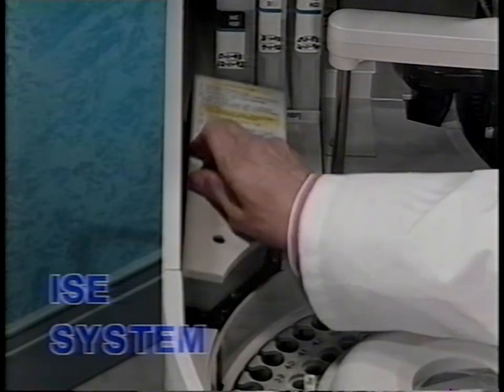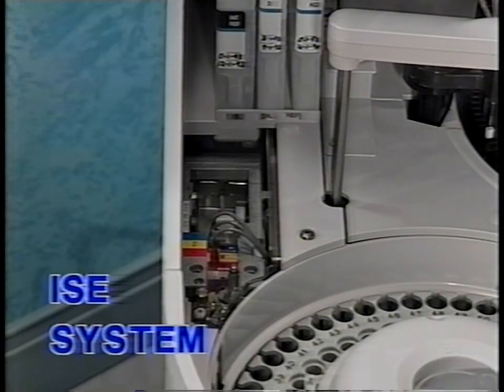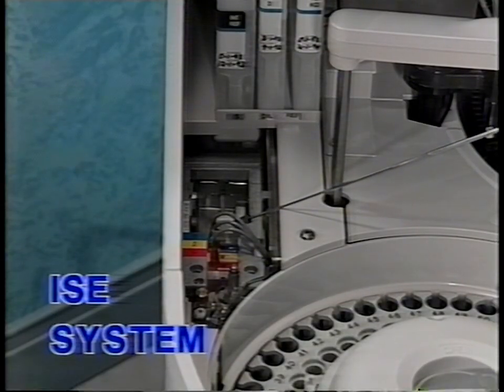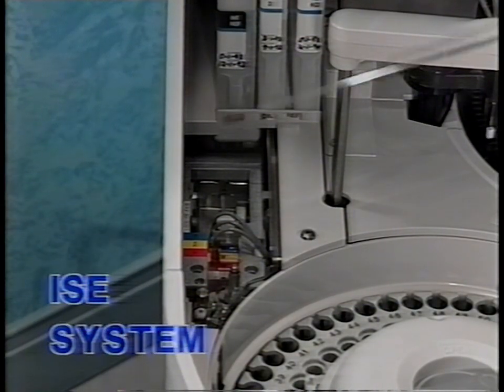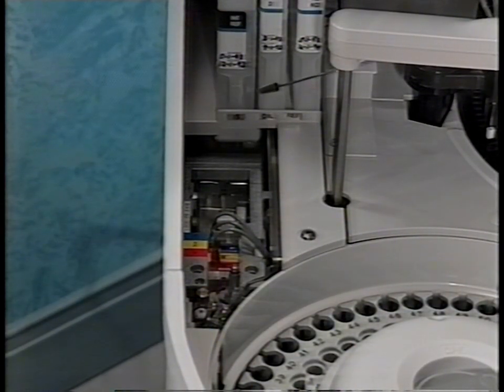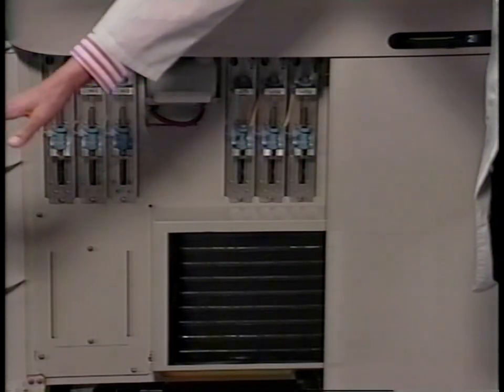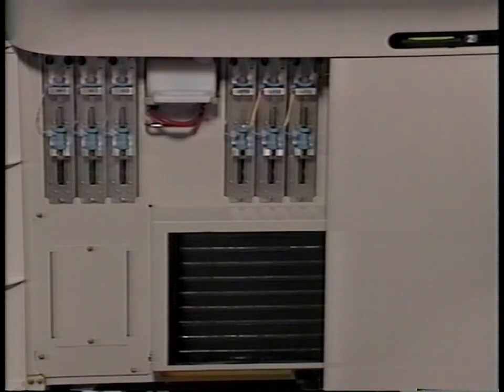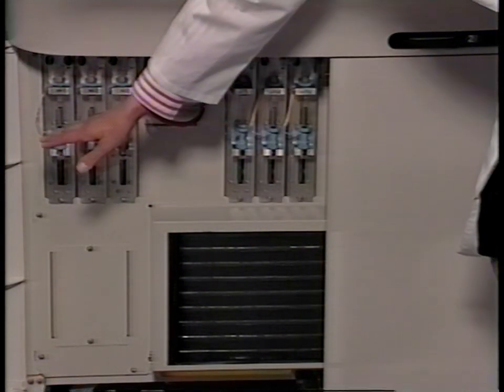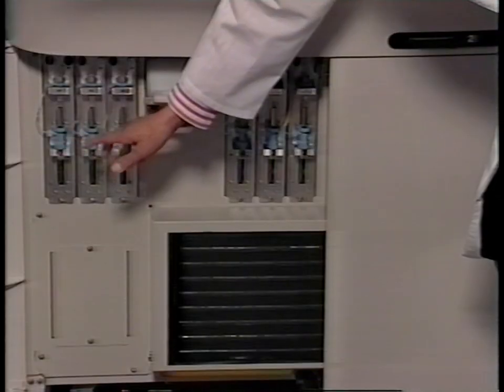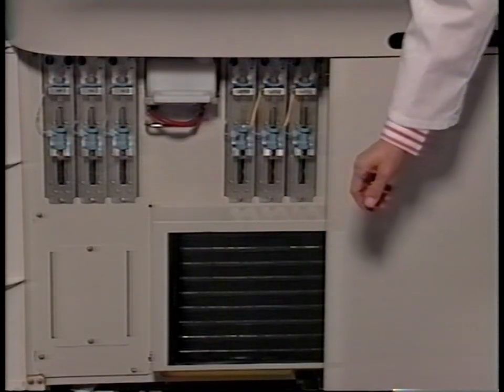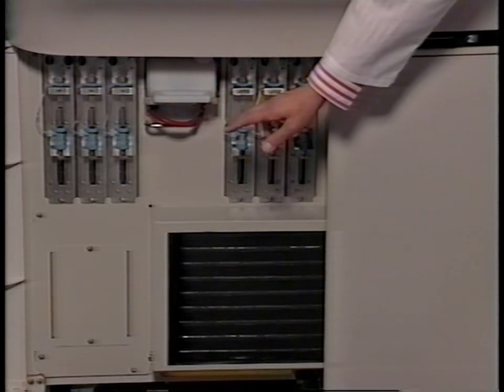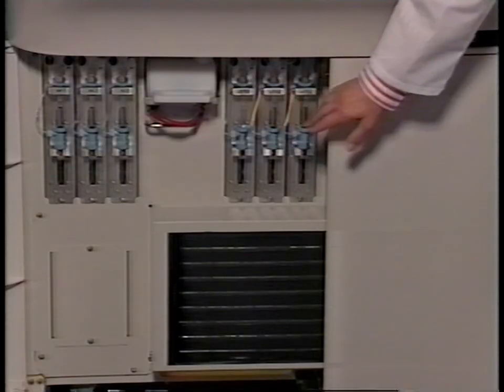The ISE system includes the sample dilution vessel, a temperature-controlled measuring assembly with 3 measuring cartridges and a reference cartridge, and ISE reagents. The 3 ISE pipetters, the internal reference, diluent, and the sipper, are located in this compartment here on the left. The sample and photometric reagent pipetters are also located here on the right.